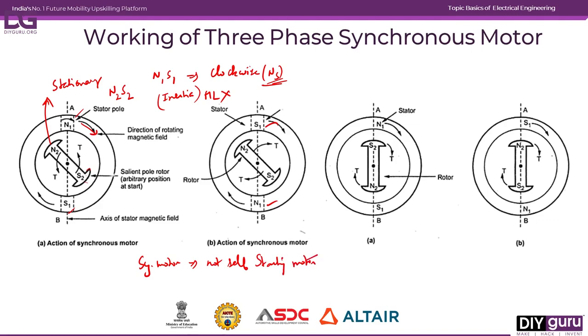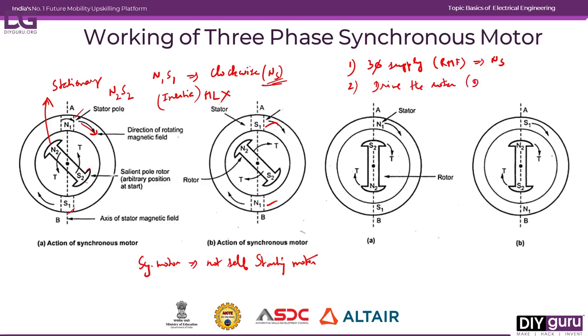Some modification is needed to rotate the rotor to come into contact with the stator poles so that magnetic locking takes place. Once magnetic locking takes place, the rotor will rotate at the speed of the rotating magnetic field. The procedure to start: first, give a three-phase supply to the stator to produce the rotating magnetic field. Second, drive the rotor by some external means — such as a diesel generator or a small auxiliary motor.